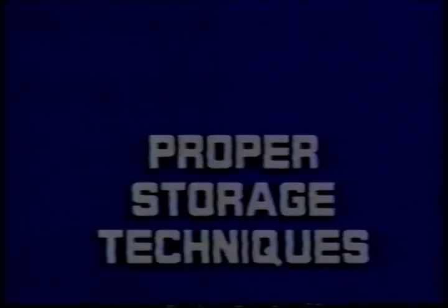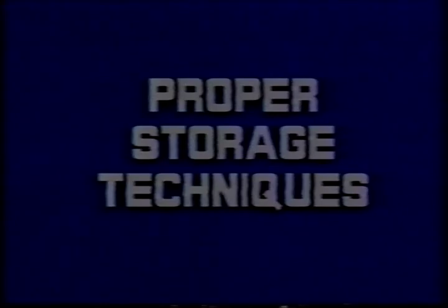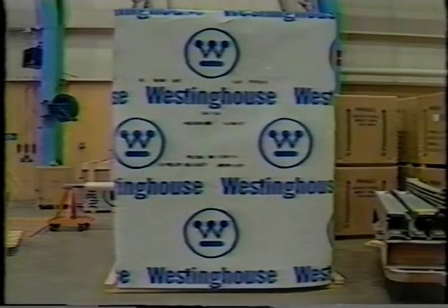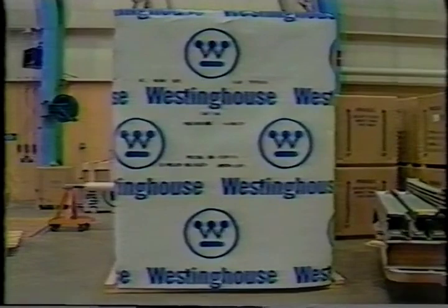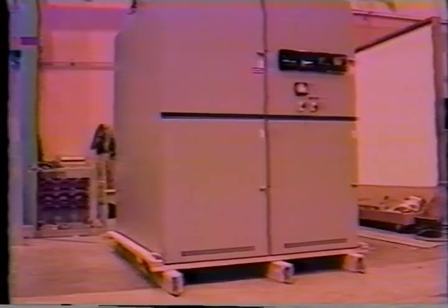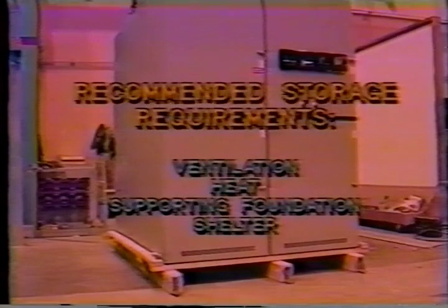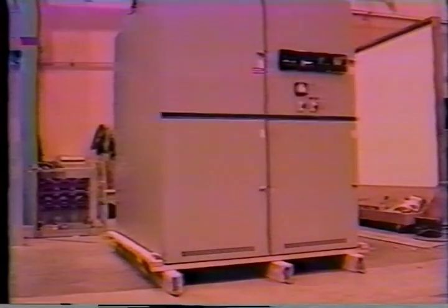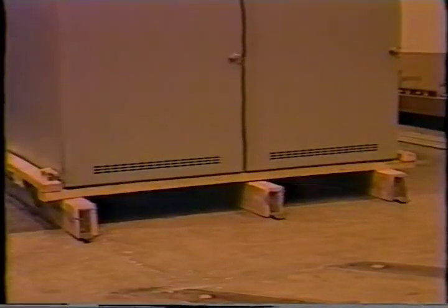If the switchgear is to be installed immediately, the following steps on proper storage techniques may be omitted. Packaging for shipping is not suitable for storage. A suitable storage place should be prepared. The switchgear should be stored indoors in a heated building that is clean and dry. The floor should be smooth and level and well drained to prevent standing water. The switchgear should be stored on skids to keep it off the floor and to allow for the free movement of air underneath it.